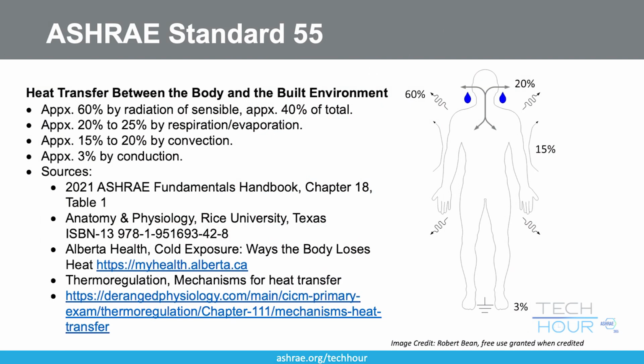One thing we like to draw attention to is how the human body responds to the thermal environment, which can create conflict in discussions. But we know through ASHRAE handbooks, medical textbooks, and indoor environmental guidebooks that the body's sensible relationship with the indoor environment is predominantly radiant. Convection plays a role, as do respiration, evaporation, and conduction, but of the sensible load, approximately 60% of that exchange is radiation—or 40% of the total exchange.